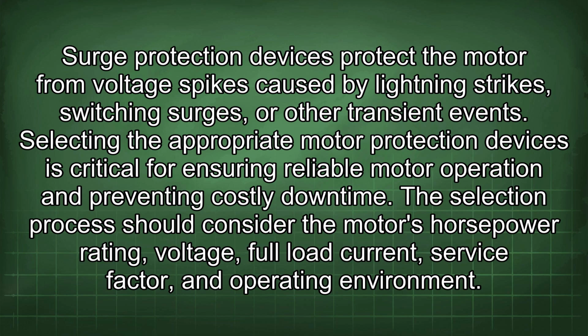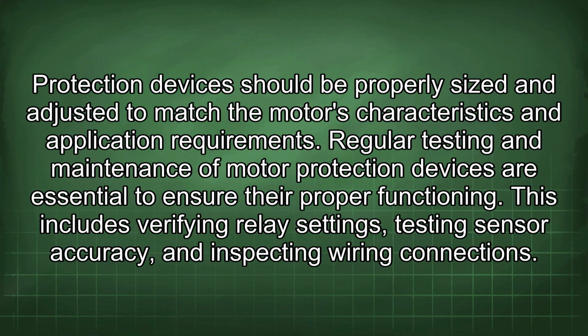The selection process should consider the motor's horsepower rating, voltage, full load current, service factor, and operating environment. Protection devices should be properly sized and adjusted to match the motor's characteristics and application requirements. Regular testing and maintenance of motor protection devices are essential to ensure their proper functioning. This includes verifying relay settings, testing sensor accuracy, and inspecting wiring connections.